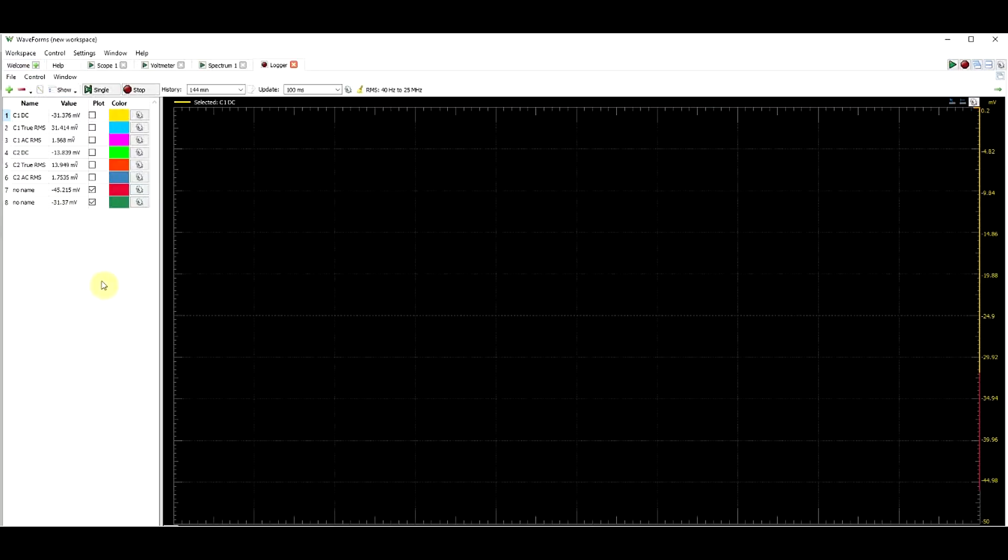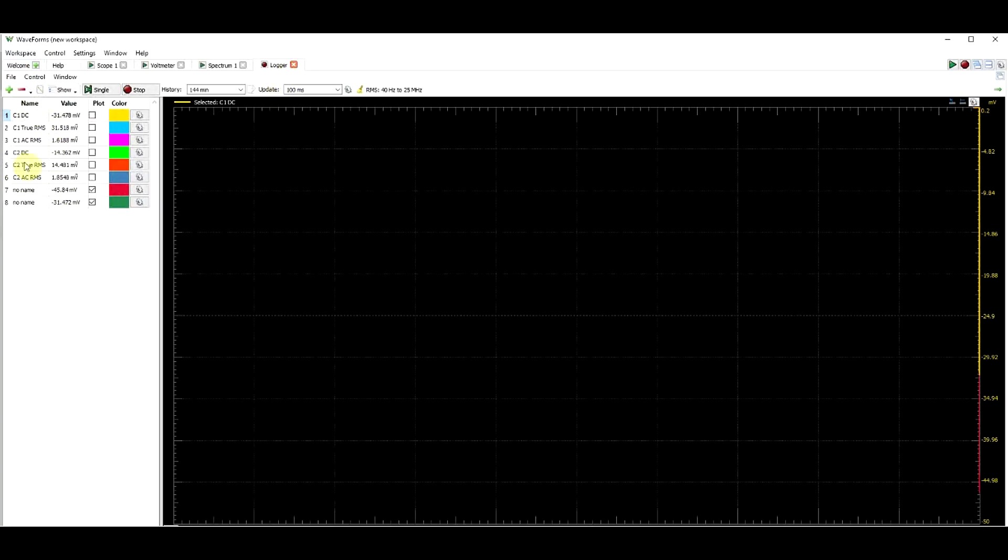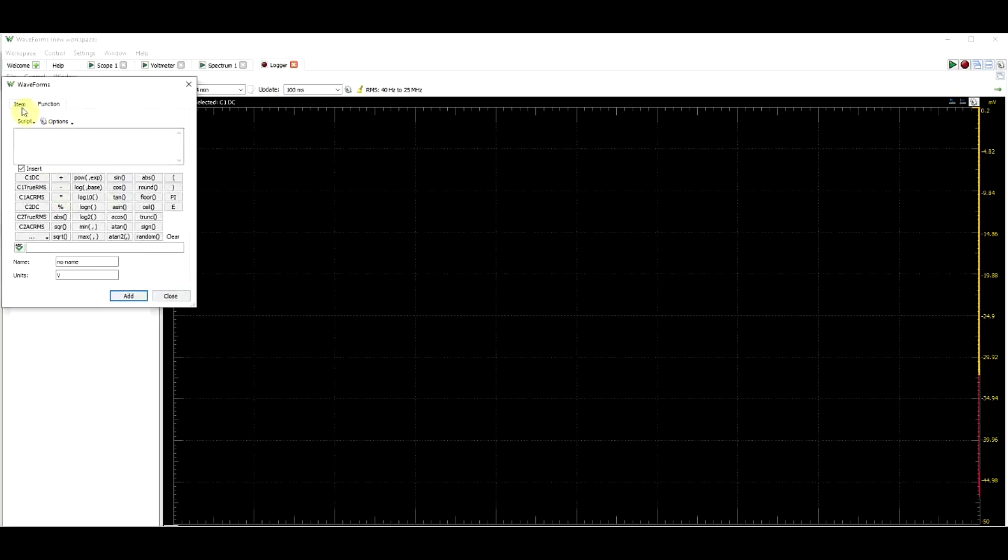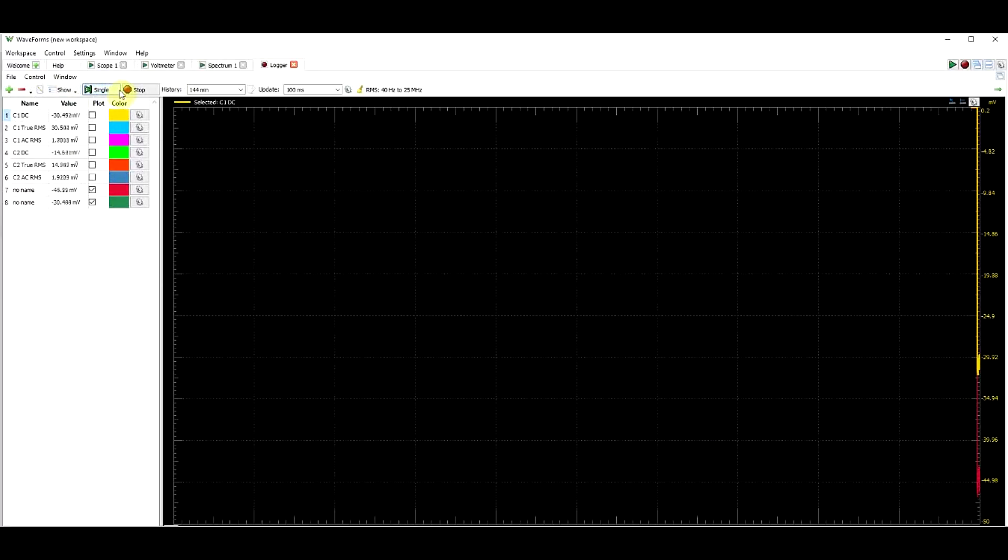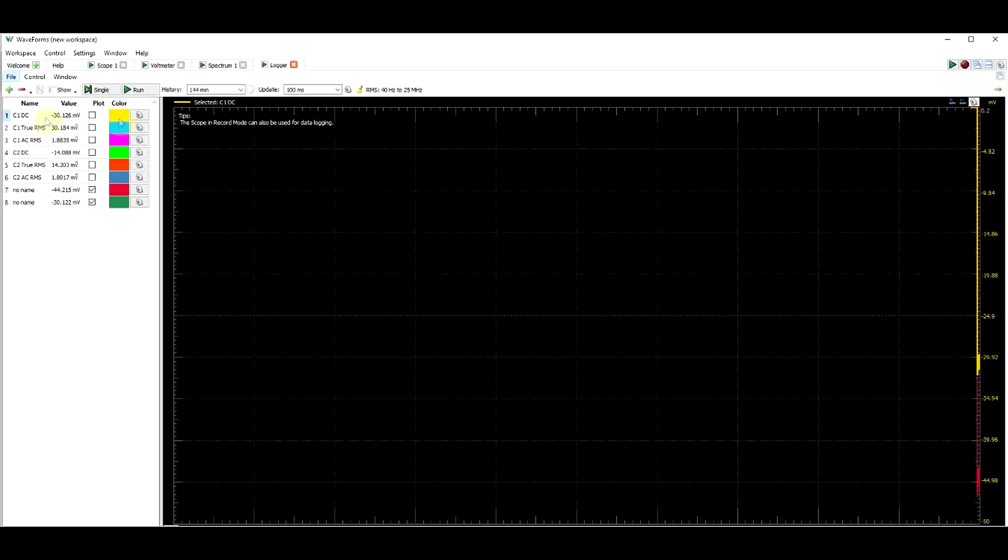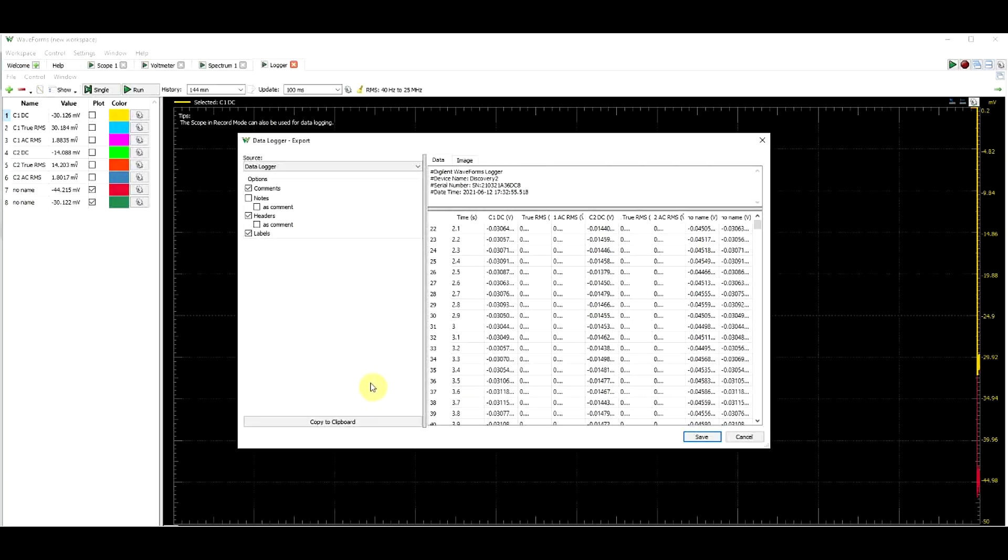Finally, with the oscilloscope channels, you have your data logging option. So here you can set the various measurements that you could set with the oscilloscope, including functions where you can combine various measurements with various operations, and then simply plot this over an extended period of time to see how your measurement evolves. And with all of the measurements, of course, you have the option of exporting these. So you have all of the measurement points, you can export this as a CSV or something. So the data doesn't just sit in the program, you can export it and do further processing with it.